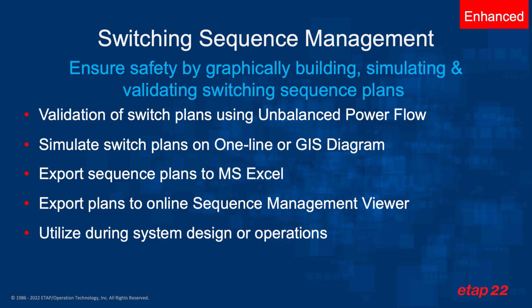Switching sequence management allows users to ensure safety by graphically building, simulating, and validating switching sequence plans. These validations of switch plans use unbalanced power flow, and now in ETAP 22, you can simulate switch plans on the one-line diagram or the GIS diagram as well. You can export these sequence plans to Microsoft Excel, or you can export the plans to an online sequence management viewer provided as part of the ETAP real-time solution. Therefore, you can use switching sequence management not only during system design, but also during operations and maintenance.